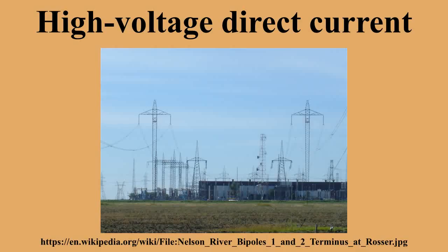A high-voltage, direct-current electric power transmission system uses direct current for the bulk transmission of electrical power, in contrast with the more common alternating current systems. For long-distance transmission, HVDC systems may be less expensive and suffer lower electrical losses. For underwater power cables, HVDC avoids the heavy currents required to charge and discharge the cable capacitance each cycle. For shorter distances, the higher cost of DC conversion equipment compared to an AC system may still be justified, due to other benefits of direct current links.